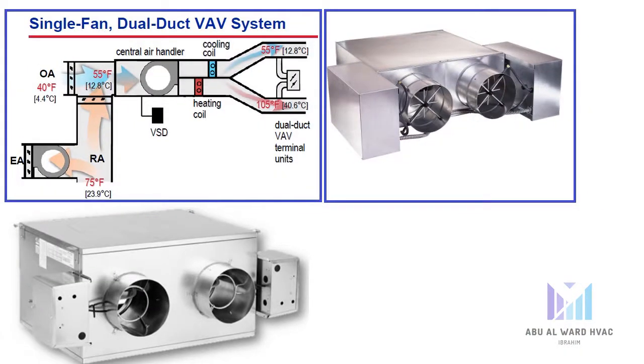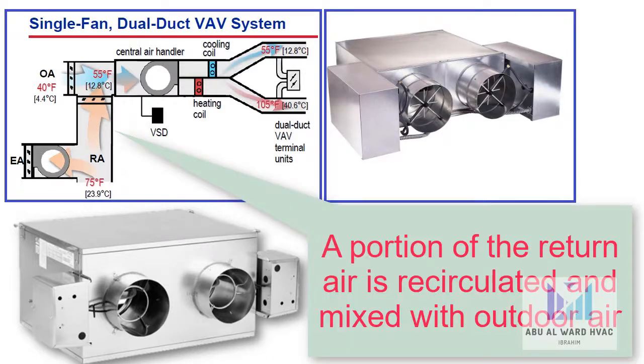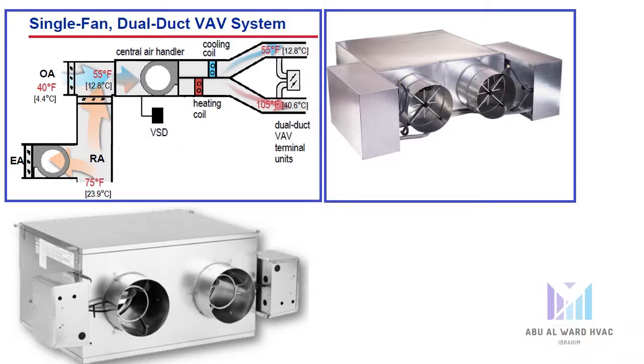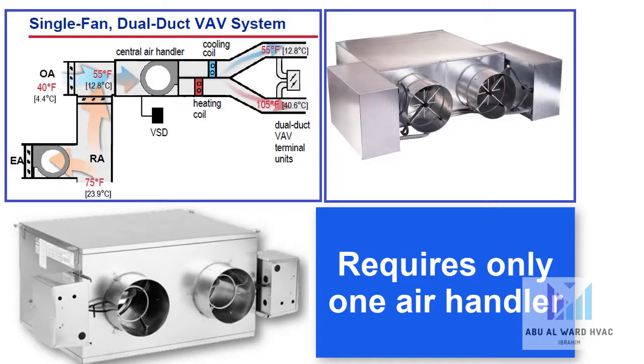First, the single fan dual duct VAV system configuration. At the single air handler, a portion of the return air is recirculated and mixed with outdoor air. This mixture of outdoor and recirculated return air is then diverted through either the cooling coil or the heating coil, and delivered down the respective duct system to the dual duct VAV terminal units. While this single fan configuration requires only one air handler, it is very complicated to control effectively.